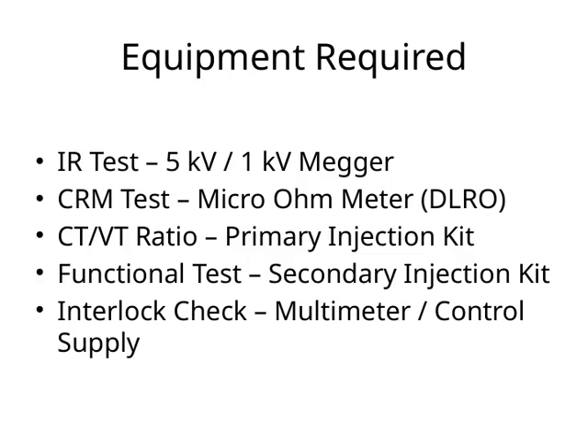Moving on, for the CT and VT ratio tests, a primary injection kit is necessary. This kit allows us to inject a known current directly into the transformer to verify the ratio accuracy of current and voltage transformers. For the functional test, we use a secondary injection kit to simulate the operation of protective relays and ensure they respond correctly under actual conditions. Finally, for the interlock check, a multimeter or a control supply is required. This helps us verify that interlocks are functioning properly, preventing unsafe operation and ensuring system safety. All these tools are vital for comprehensive testing, ensuring our equipment performs reliably and safely within the overall system.